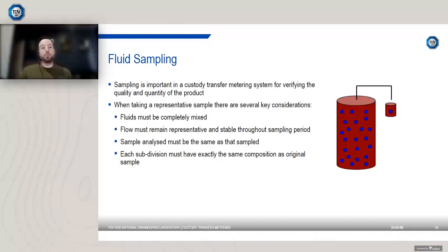Now, whenever you take a sample, there are several key considerations. First is the flow must remain mixed. So if you've got oil and water in your system, they have a tendency to separate out. The water sits in the bottom of the pipe, the oil sits in the top. Now, if you sample from the top of the pipe, you're just going to be drawing off oil. So whenever you take a sample, you need to ensure that the fluid remains mixed. It's important that the flow remains representative and stable throughout the sampling period.